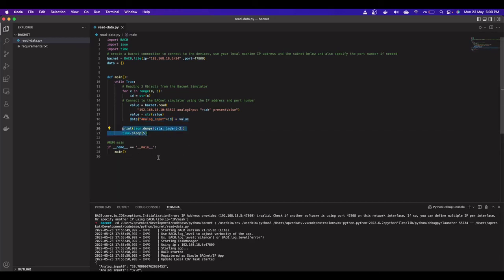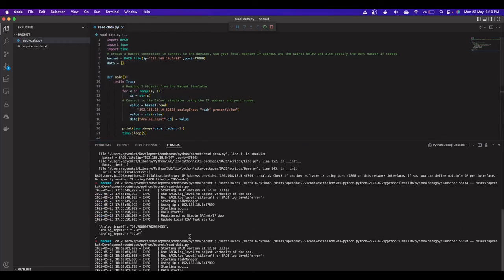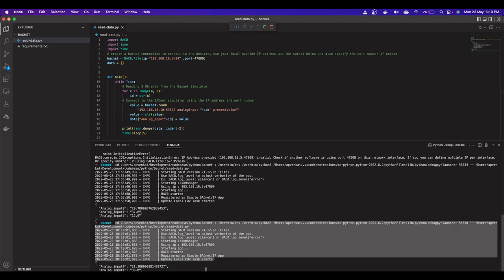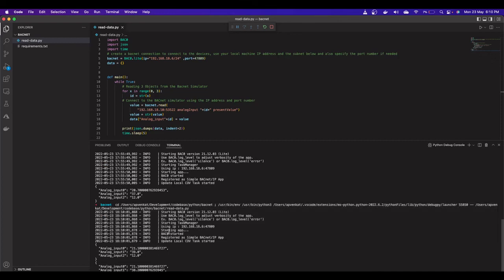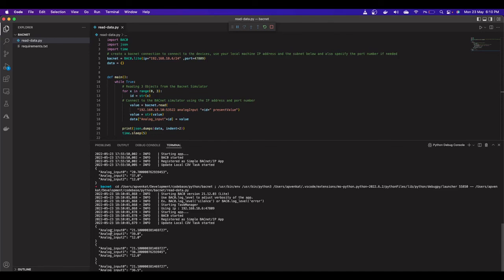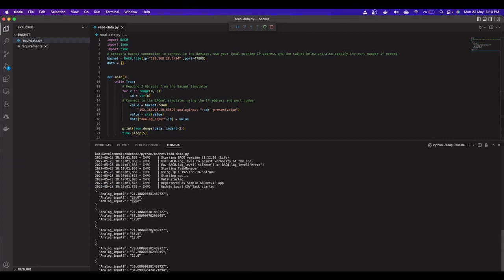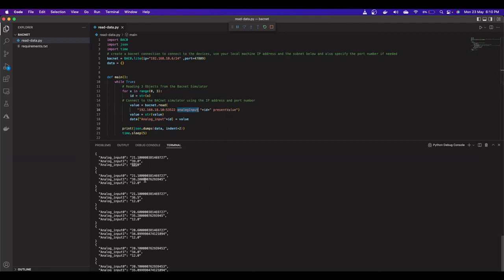Run the program. The BACnet device is detected and every five seconds the program polls the BACnet simulator. The output shows: Analog Input 0 is 21.1°, Analog Input 1 is 39°, and Analog Input 2 is 12° — matching what we saw in the APE simulator. You can extend this to specify lists of ports, objects, and properties, appending everything into a single JSON dictionary or array as needed.